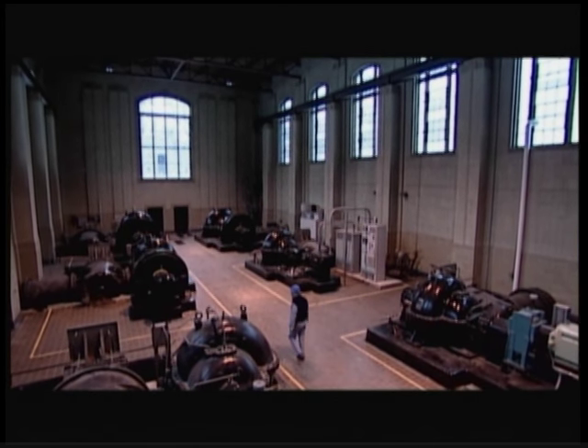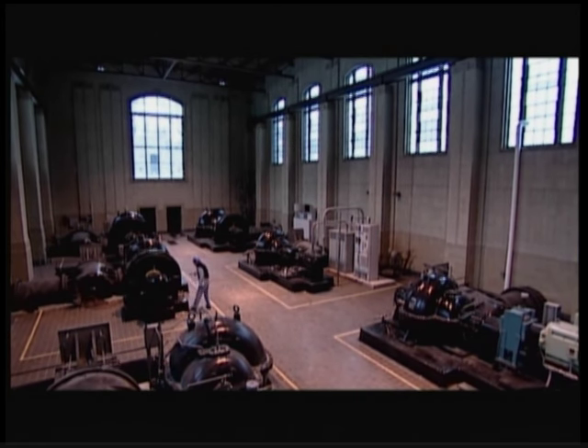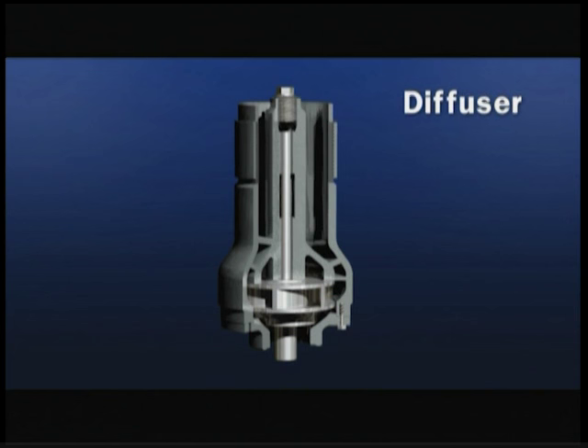Velocity pumps use a spinning impeller or propeller to accelerate water to high velocity within the pump casing. This is achieved in one of two different ways: in a volute or expanding spiral casing shape, or through diffuser vanes or channels such as those built into the bowls of vertical turbine pumps.